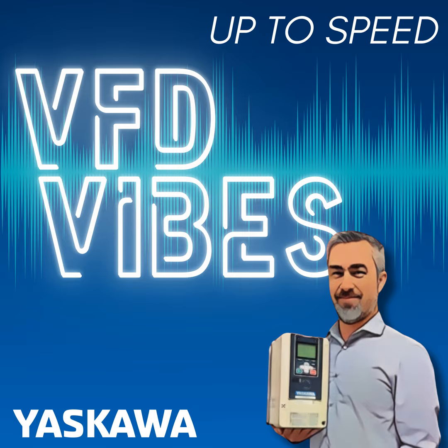Type 1 is designed for an indoor location, clean environment, conditioned air. We don't have rapid temperature changes. There's no condensation forming, no dripping water pipes or water spray, anything like that. If you had, let's say, an office location with conditioned air, a type 1 drive, you could put a type 1 drive on the wall in that condition, or a clean mechanical room, something along those lines.